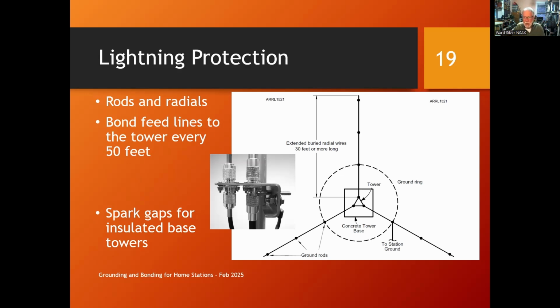I don't know too many coaxial cables whose jackets are rated for 100,000 volts. So what happens is the cable is destroyed, or you get pinholes, or you get splits in the jacket from the various arcs. So you want to bond your feed line to the tower every 50 feet using some kind of bonding bracket or a bonding kit from a hardline manufacturer. And yes, it's a pain in the neck. You've got to put extra connectors on it, and you've got to waterproof them and all that stuff. But that keeps your system intact when it's stressed by a lightning strike, either direct or nearby.